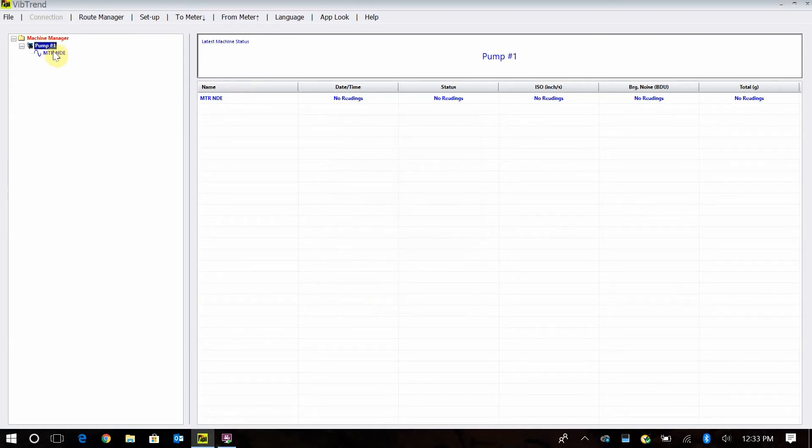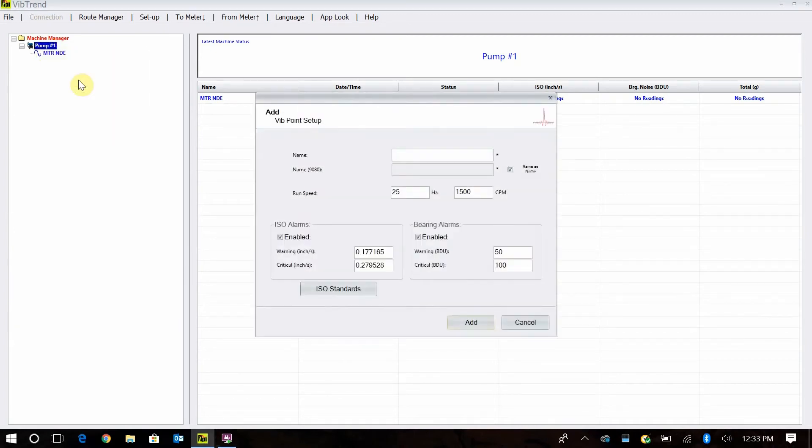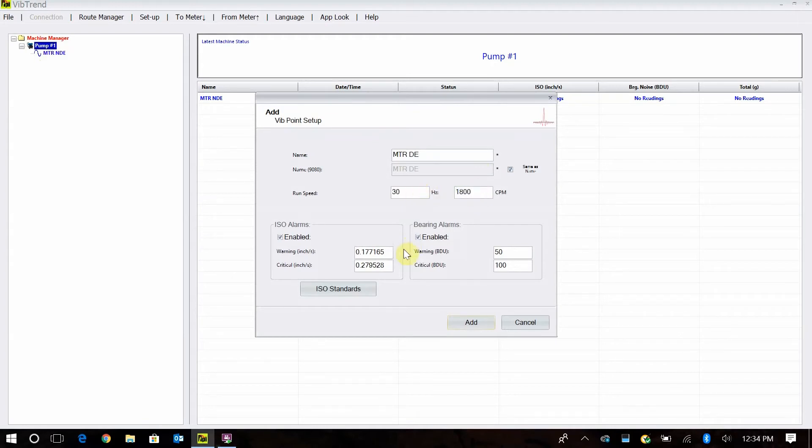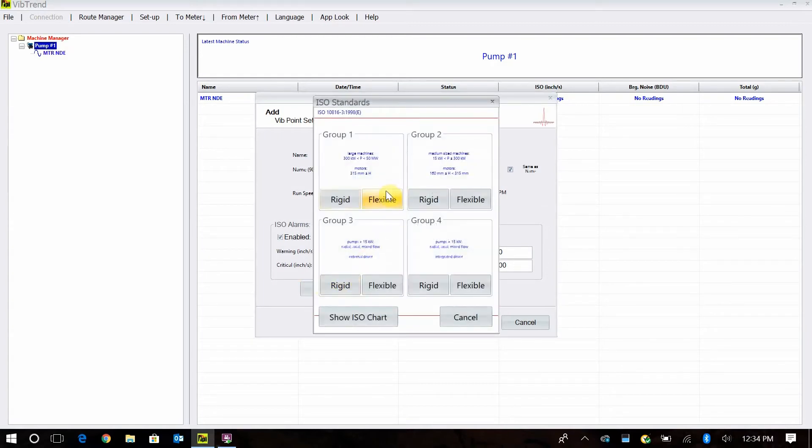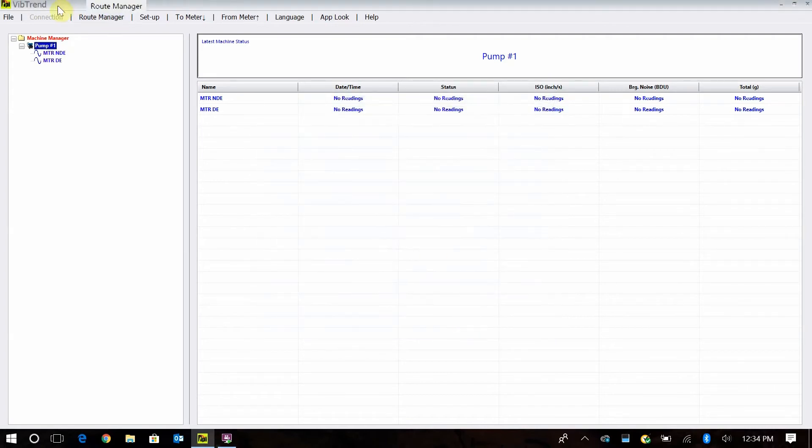After your motor non-drive end, the next thing you want to do is add a motor drive end reading. I just right click, add vib point. Same thing, I'm going to put in MTR for motor and then DE for drive end. And then 1800 is my speed. And then once again, I go here, my ISO standard, group one flexible, and 50 and 100 for my bearing damage unit alarm level. And I tell it to add.